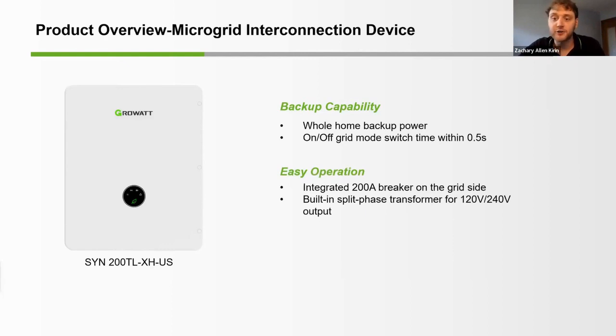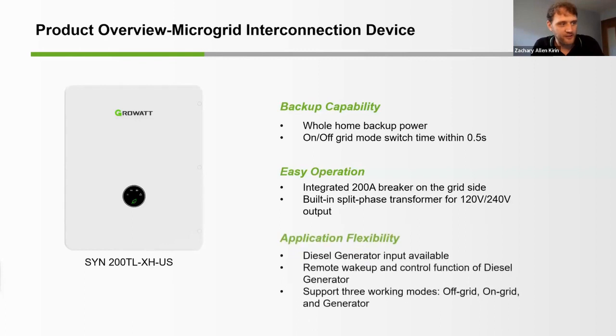It is service entrance rated with a built-in 200 amp grid side breaker and has a split phase transformer to power 120 volt loads as well. It handles the same phase imbalance of 3000 watts, but the SYN can be utilized with the feeder conductors of the home and features that integrated 200 amp breaker. This is very important. It is service entrance rated, so the feeder wires can be put directly to the SYN. And we'll show you a little bit more about how we're working together in the next few slides.